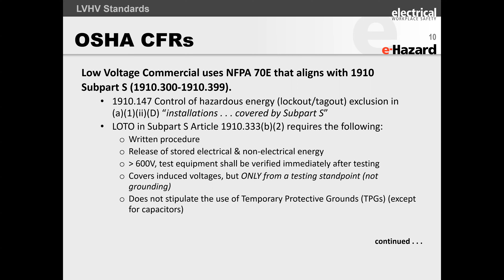Going on, if you look at Article 333, which talks about work practices when you're working on or near equipment, it says this is limited to qualified persons, and refers to 1910.269 for these work rules. They tell you that if you're high voltage qualified, you are unqualified to work on low voltage, and if you're low voltage qualified, you are unqualified to work at higher voltage. So anybody who is not high voltage qualified needs to maintain at least 10 feet clearance for voltages up to 50,000 volts.